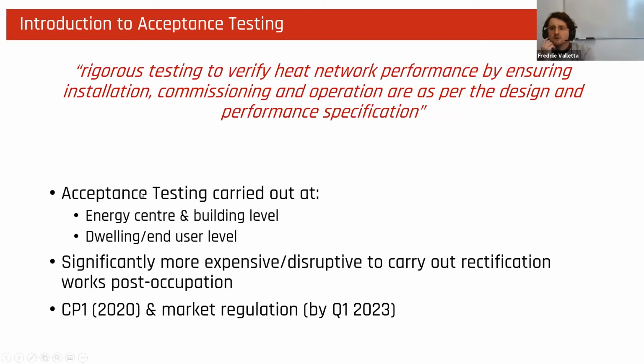So moving on to the process of the acceptance testing. This is something that we've developed at FairHeat over the last 5 to 6 years. Acceptance testing, we've come up with this definition which shows that it's rigorous testing to verify your heat network performance, ensuring installation, commissioning, and operation are as per the design and performance specification.